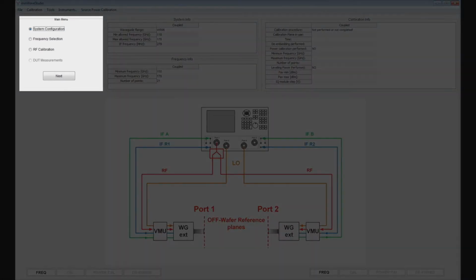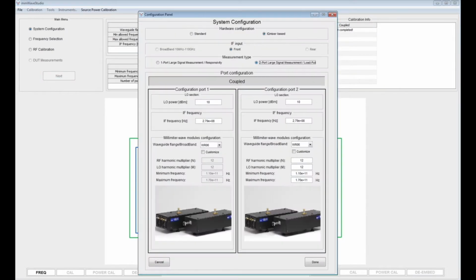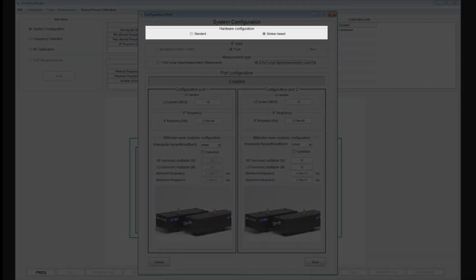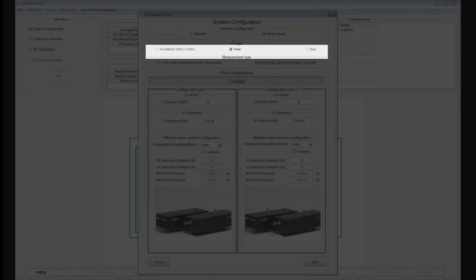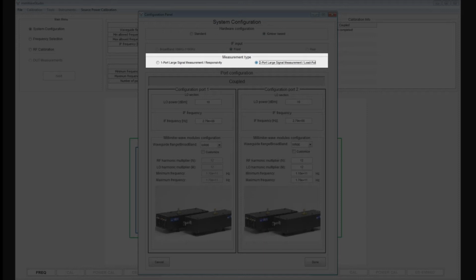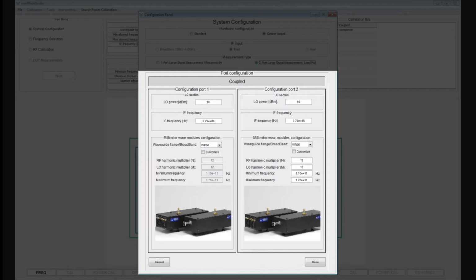To do that, we select System Configuration in the main menu and click Next. A configuration panel opens up where we can specify whether we are using the system in a standard millimeter wave configuration just by employing the frequency extenders, or if a VMU (vector modulation unit) is also used. Then we specify whether we will be performing 1-port or 2-port measurements.